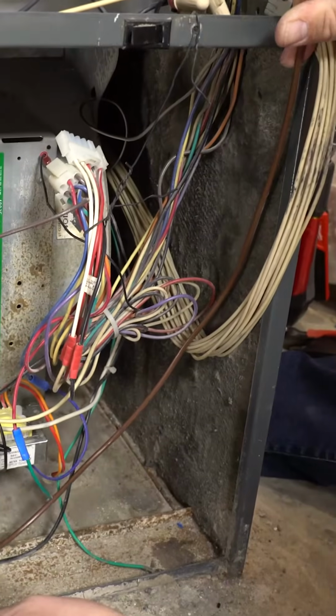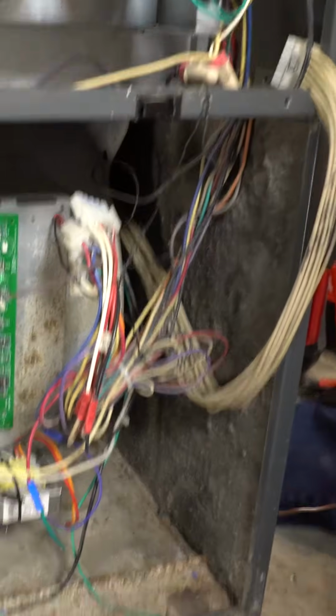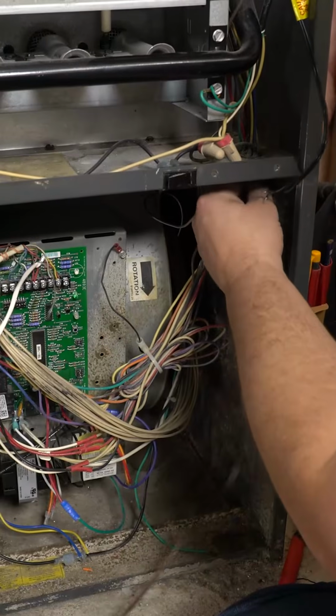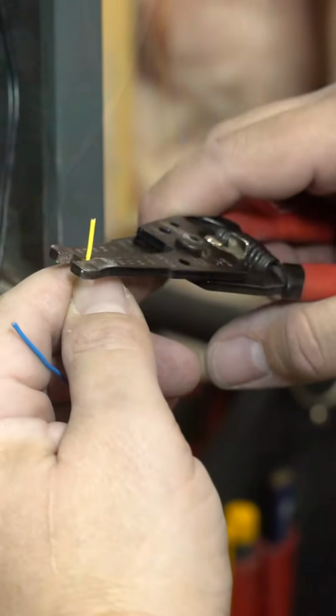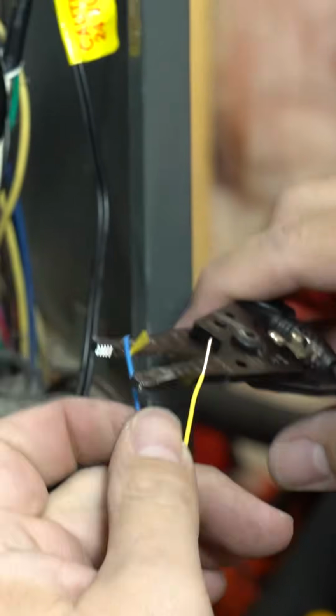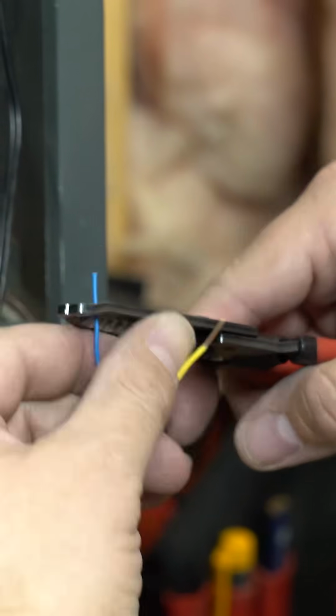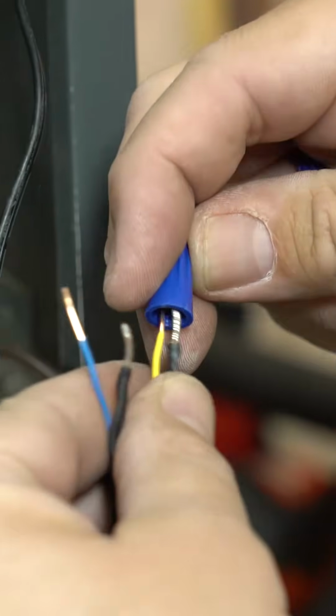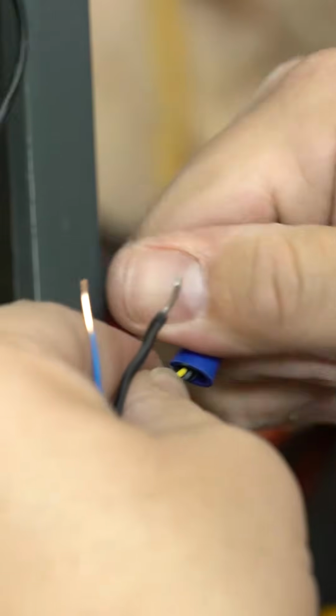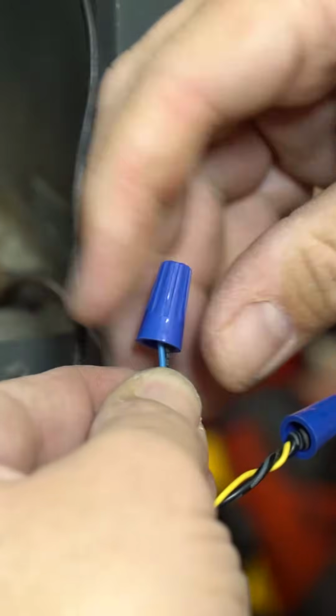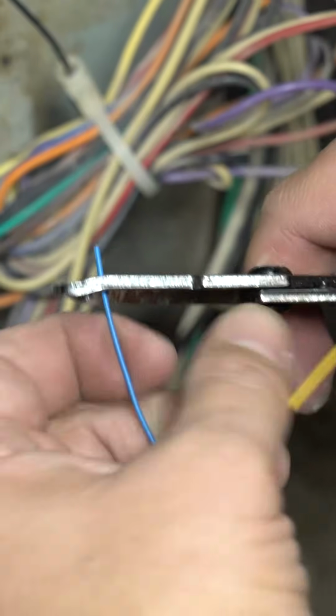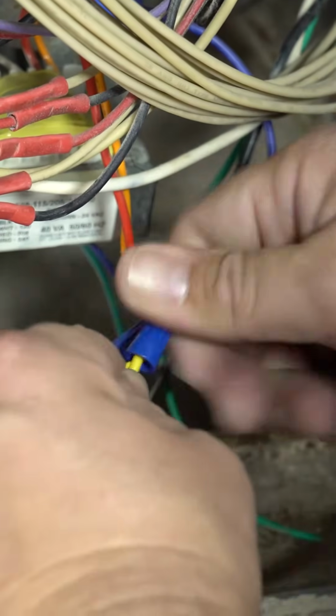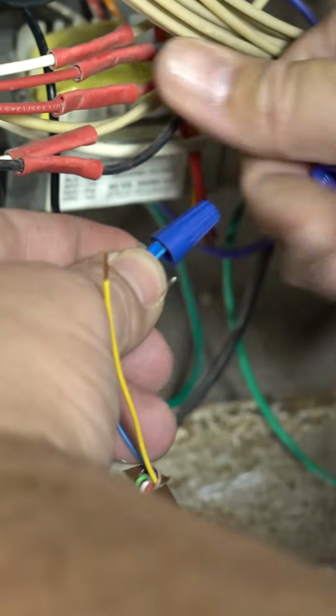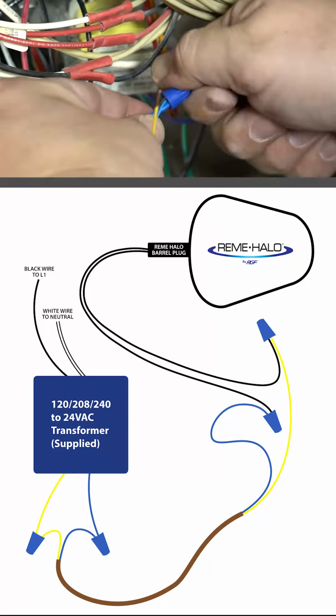The wires on the transformer aren't long enough to reach the Reme Halo using the supplied power cord, so I'm going to use some thermostat wire to extend it. Since I used the thermostat wire, I'm going to use the yellow and blue connectors to keep things consistent with the colors of the wires coming off the low voltage side of the transformer. Strip the wires and wire nut them to the power cord. It doesn't matter which wire goes to which on the power cord. Next, strip the other end of the thermostat wires and wire nut them to the corresponding colors, yellow to yellow and blue to blue. Here's a diagram to show you what I did.